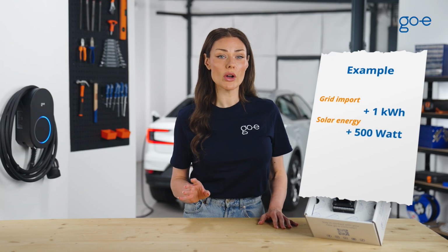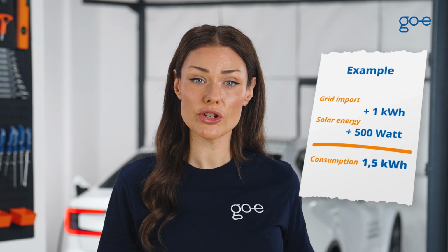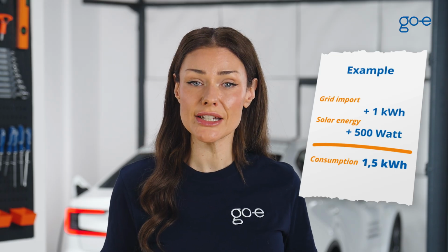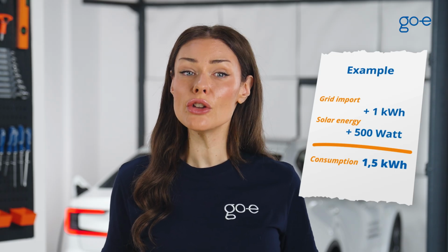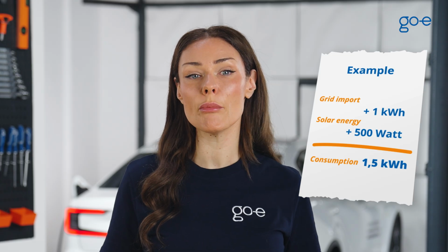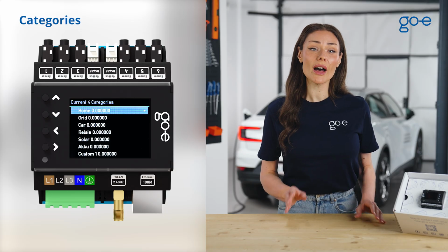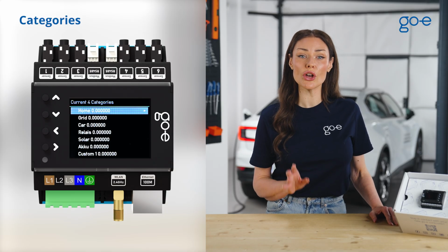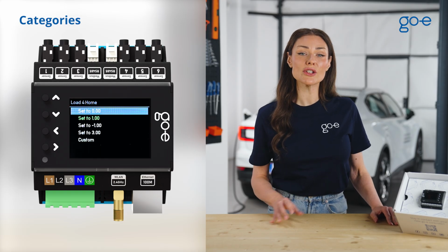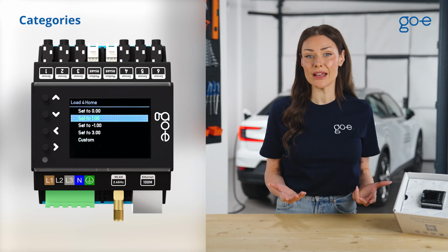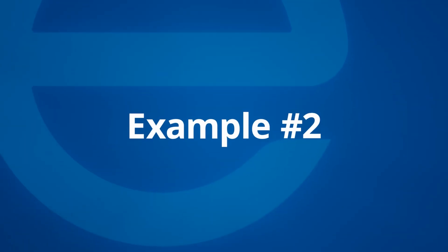Now, we also need to assign the solar power to the home category. Let's take a quick look at a calculation example. You're importing 1 kilowatt from the grid. You're generating 500 watts of solar energy. We've already assigned the 1 kilowatt grid import to home. Since you're producing an additional 500 watts yourself, your total household consumption is 1.5 kilowatts. Therefore, assign the PV inverter to the home category as well, with factor 1 or 3, depending on how many inverter phases you're measuring.